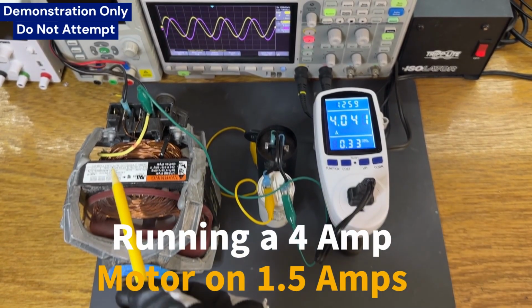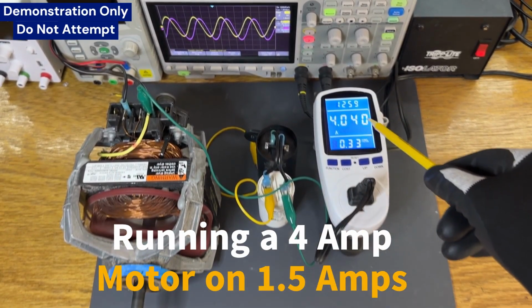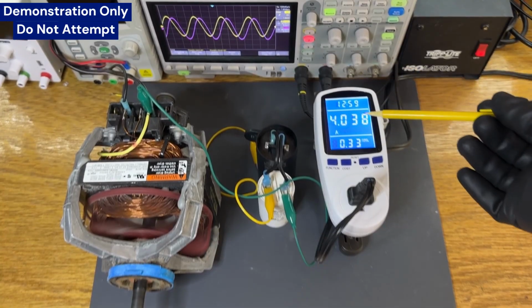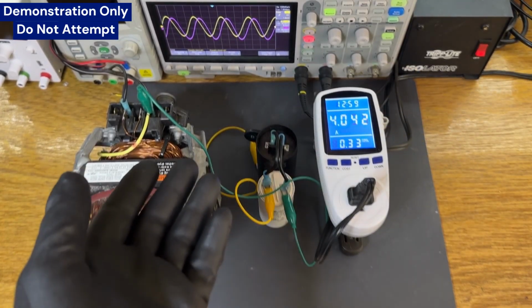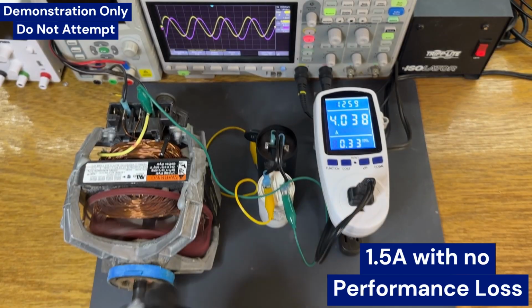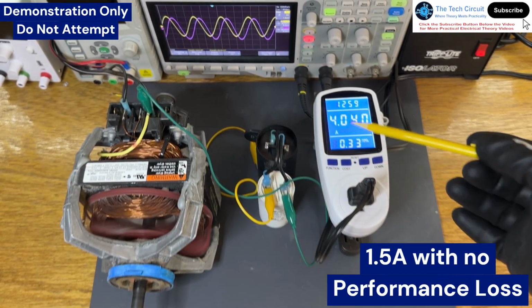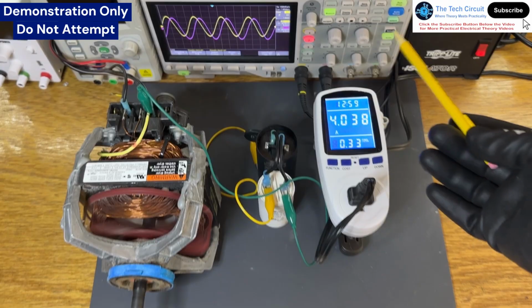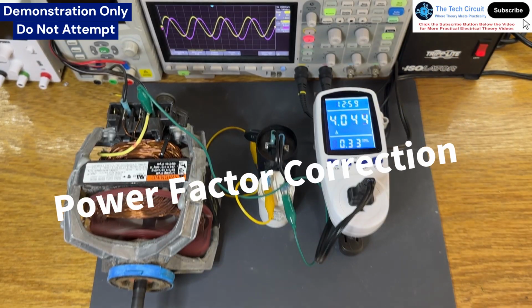This dryer motor is drawing about 4 amps of current, which is typical for this type of motor. What would you say, however, if I told you that I could reduce the current draw of this motor to about 1.5 amps with no loss in performance? In this video, we'll do just that by utilizing something called power factor correction.